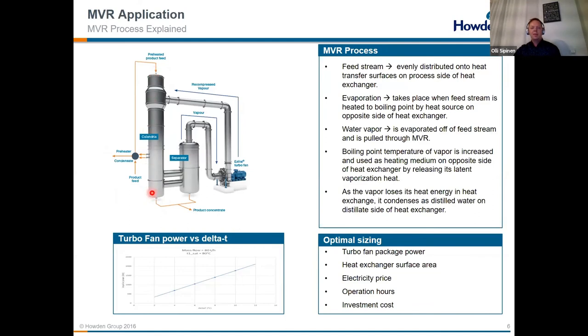So in this type of calandrias, these are full of small tubes there, where the product feed is then fed in, whatever is there made in a site, and then we will get the live steam into the system, and we'll heat this up to operational temperature there. And then instead of pushing there the new steam, we are circulating the steam inside of the system, and we are using a compressor there to lift up the pressure and temperature, which can be then fed back to the evaporator. So all the energy required for the process is then taken from the electrical network instead of producing a steam.